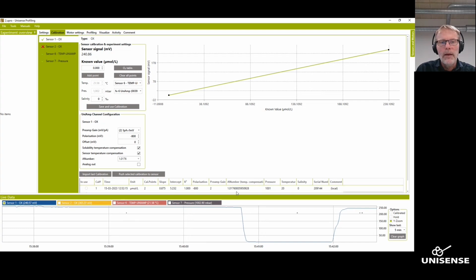changes. And that A number you can see down here, that is saved on the EEPROM on the sensor, so it's automatically loaded into the software, so it's the correct temperature compensation factor I'm using. Okay, with that said, then I'm actually ready to measure a profile.